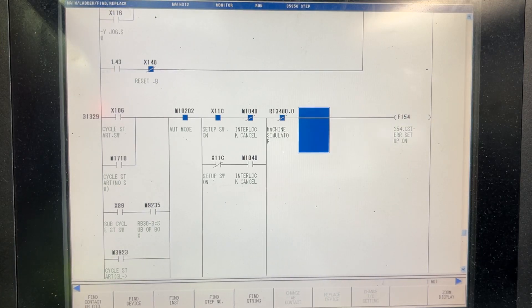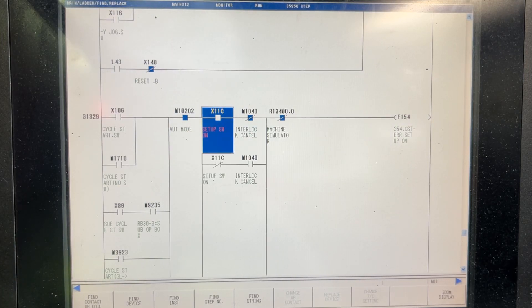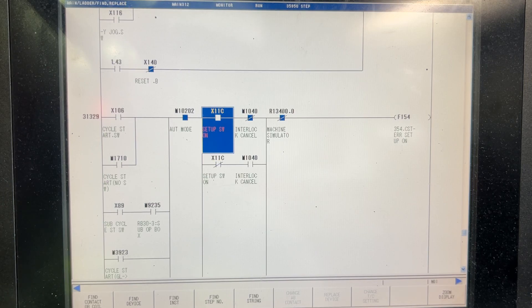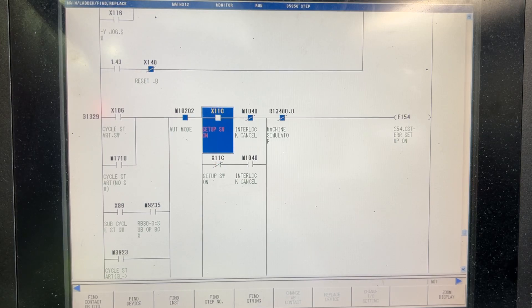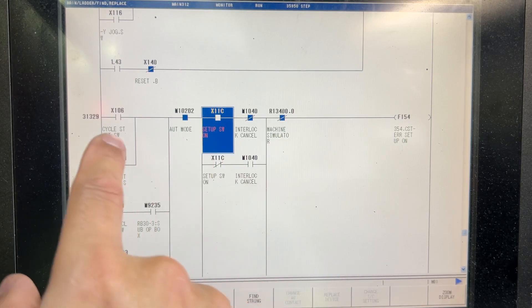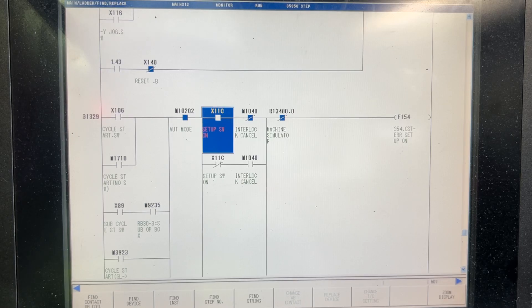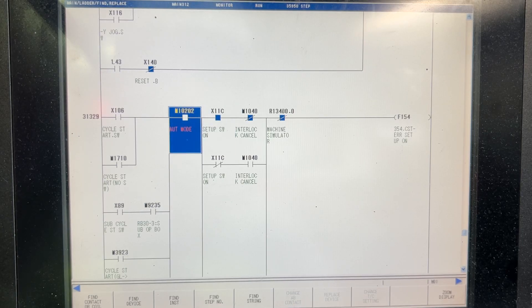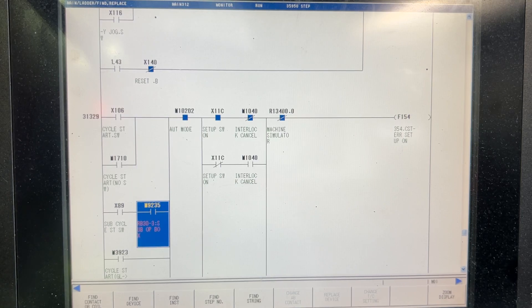Here you'll see we have the setup key in ON — so this is the setup key on the control panel. I'll switch it. If you have this condition on this signal, or any of these branches, it's going to trigger that alarm. Here we have a good example of machine parameters or PLC parameters.